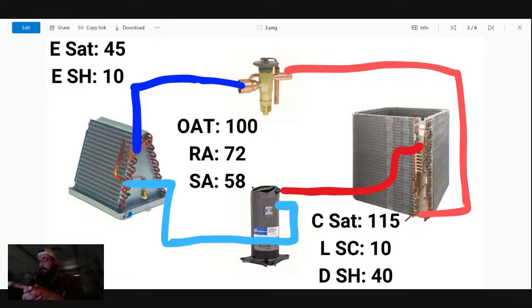Let's see. Wonder if there's a duct connection issue. The ESP isn't terrible. This one is a bit subtle, and there's some things I didn't give you here because I wanted to see if y'all could ask the right questions. So, duct connection issue. You go do an inspection.